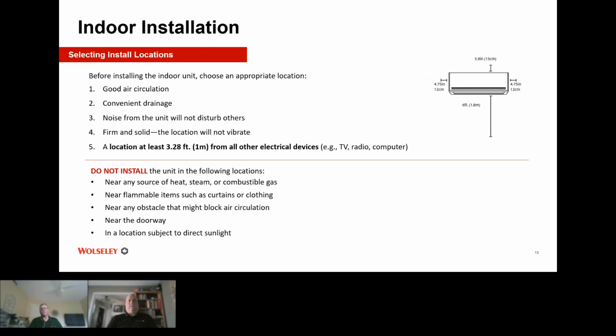You put it in a bedroom, sometimes they'll make certain noises that irritate people when they're sleeping. Make sure it's solid on the wall so there's no vibration, and make sure that it's 3.28 feet from other electrical devices, TV, radio, computer. Sometimes people will install them over top of a TV, but not a real great idea because you could get electrical interference. But if the unit ever leaks, you may be looking for a TV as well. And it'll just run down inside and blow it up.